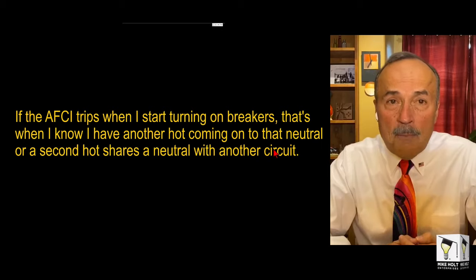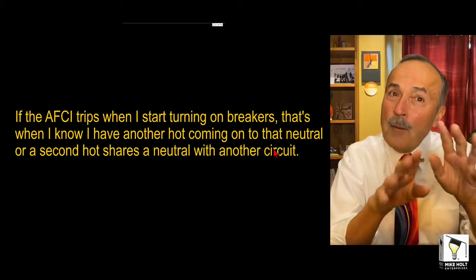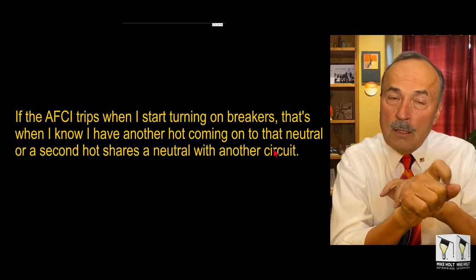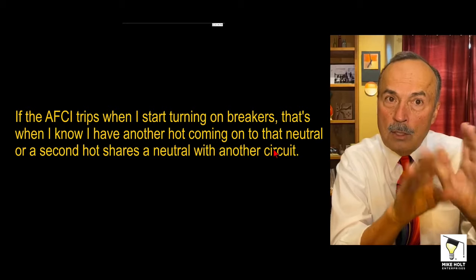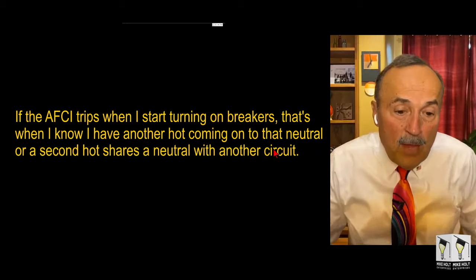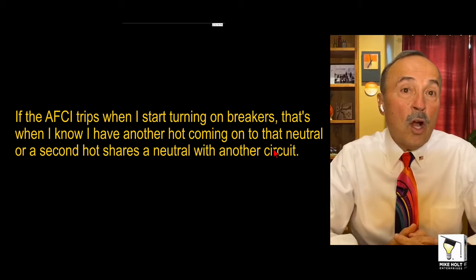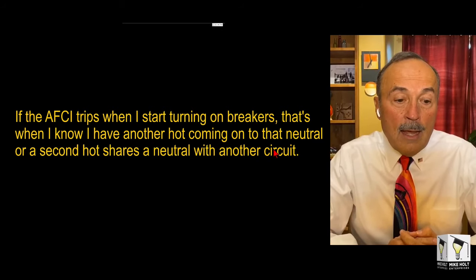Now, he was also saying, hey Mike, when I do this troubleshooting, I had a problem with that voltmeter deal. Put the current meter, the ammeter, on there. I'm good with that, and then do the other techniques. He says if the AFCI trips when I start turning on breakers, that's when I know I have another hot coming on that neutral, or a second hot sharing a neutral with another circuit.